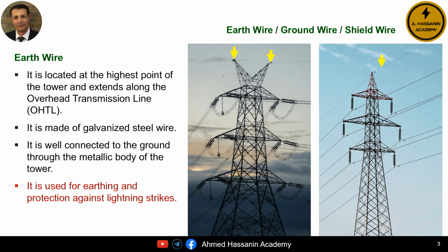Of course, we stated that the primary and fundamental function of the earth wire is to protect the overhead transmission line and the insulators installed on it from the danger of lightning strikes. For the earth wire to be able to safely discharge the lightning strike, it must be properly grounded.